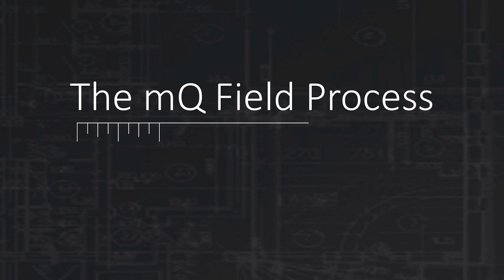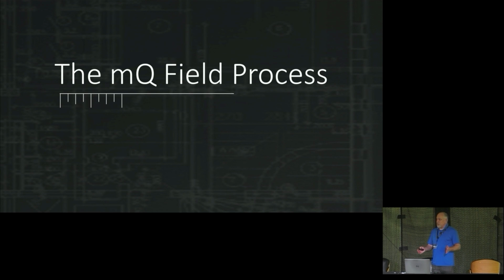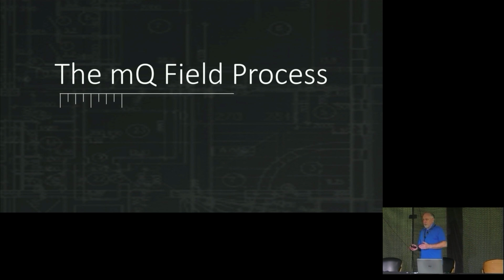So you're going, wait a minute, I thought this was going to be a MeasureQuick presentation, and it is. This is a software program. It's designed to pick up these faults and problems, but there's nothing more important than you going through that system and doing a proper visual inspection first, because there's absolutely no reason to put MeasureQuick on a system or to start deploying your probes or evaluating charge on a system with a dirty filter or dirty blower or plugged evaporator or plugged condenser.